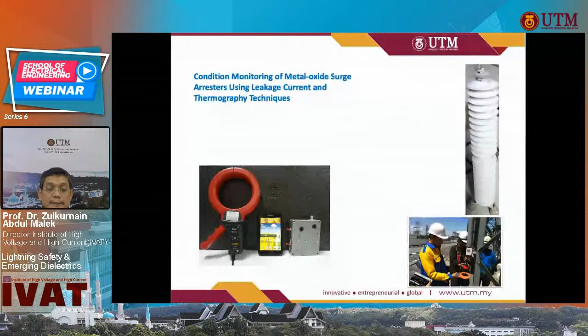So we do this using a bit of IoT, and we even use a thermal camera instead of a scanner, sorry, a clamp meter, to detect leakage current. By the way, the leakage current flowing at the bottom of the arrestor can actually indicate the aging condition of the surge arrestor. Since the more the leakage current, the hotter the body of the arrestor, we can use thermal scanners to detect the aging condition of the arresters.